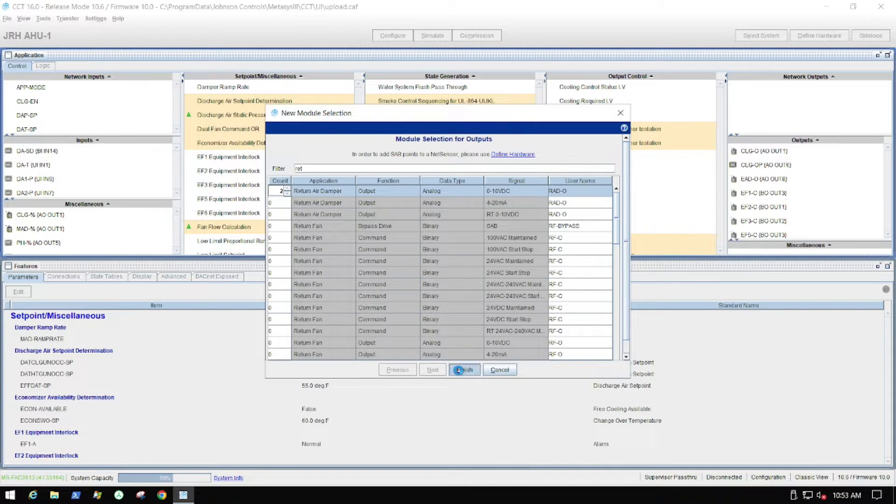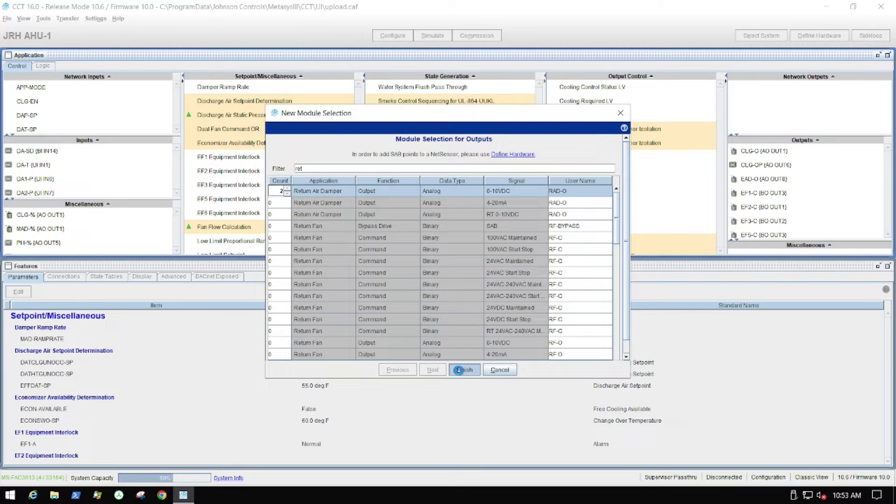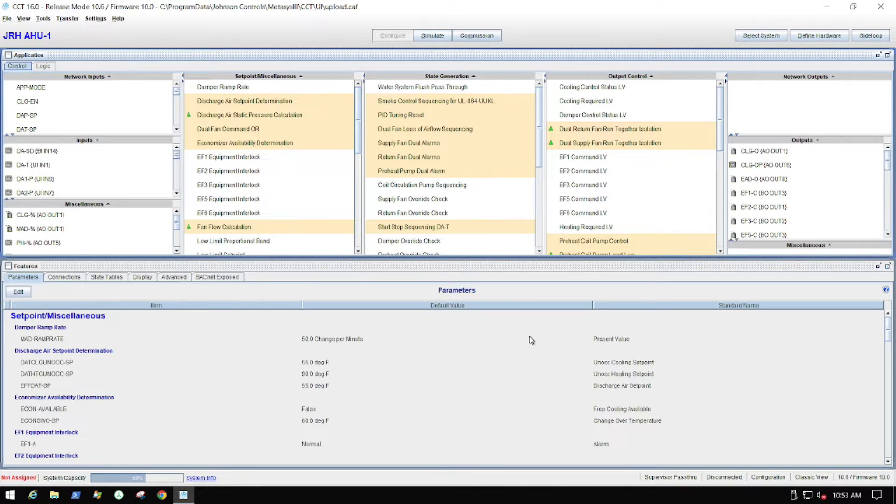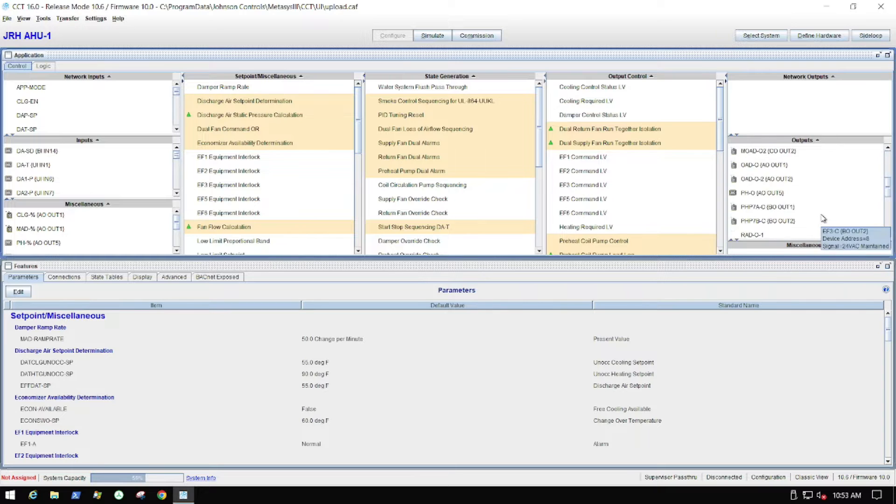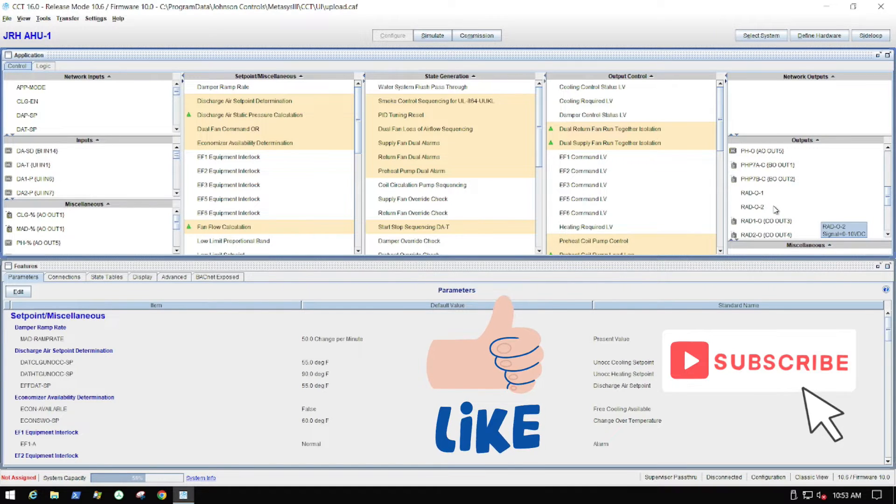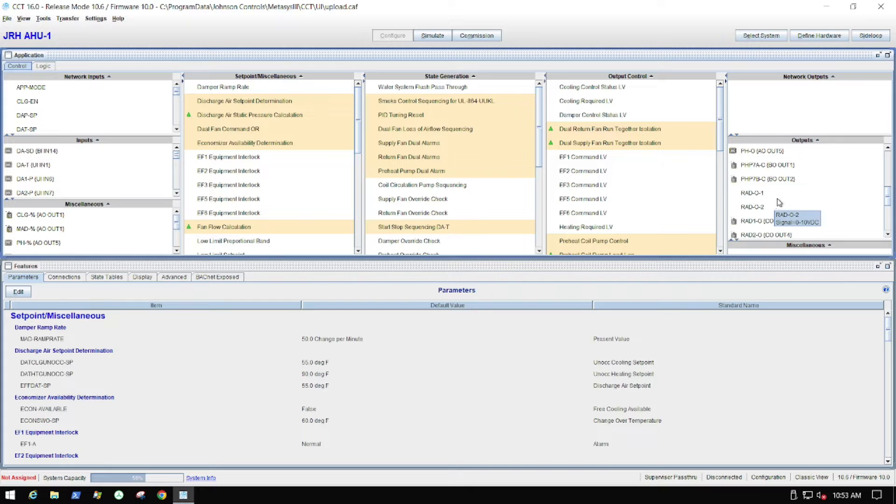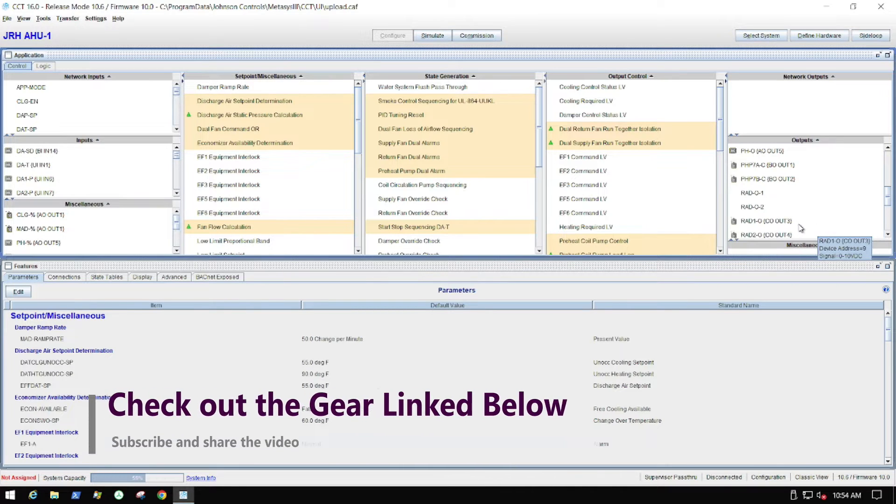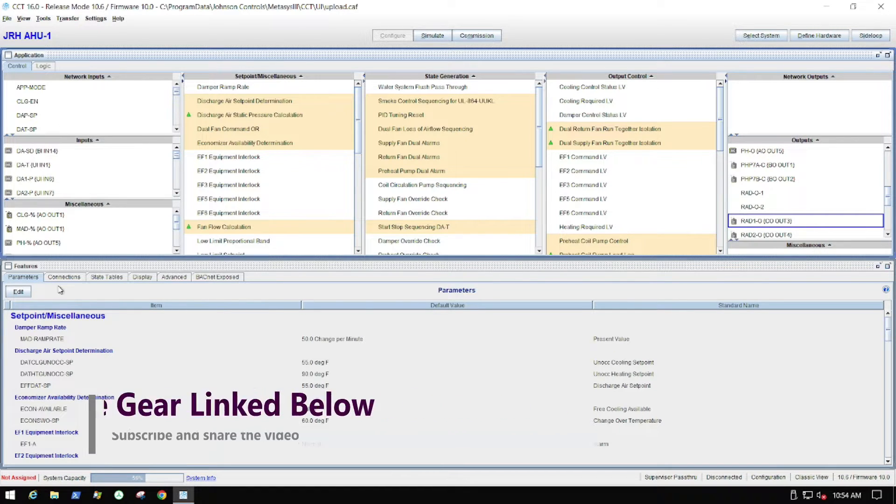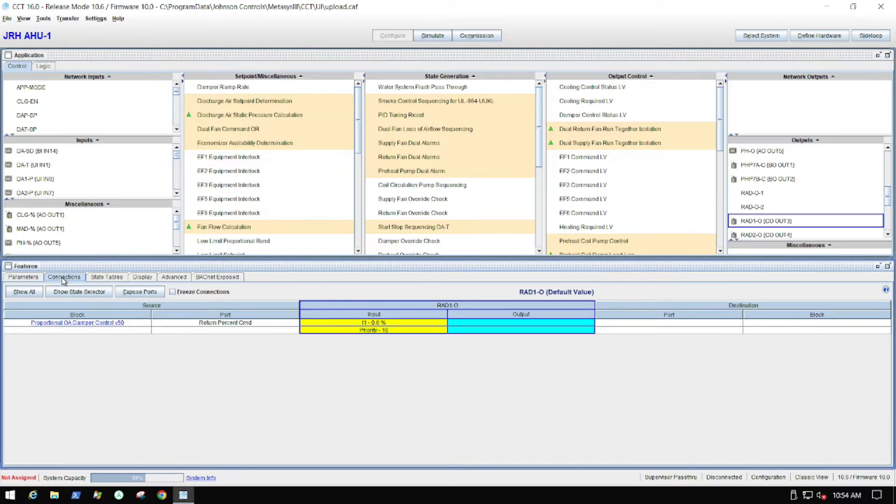This is just a brief demonstration of one aspect of this overall project. So what we're doing here is we're adding the two control points, the two additional points, and we need to tie those to the logic that already exists for controlling the return air dampers on this unit. So I'm going to simply highlight the original. You can see here I've got the two that have been added. And now I'm going to highlight one of the original points to where I can find exactly which logic block and which point controls them.